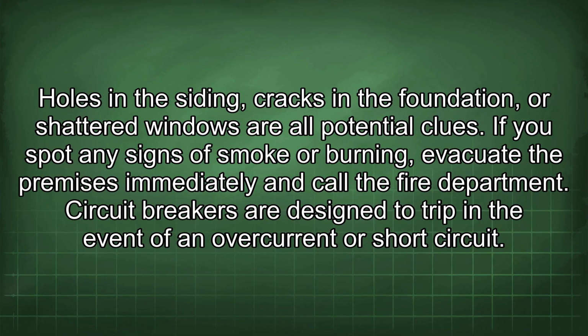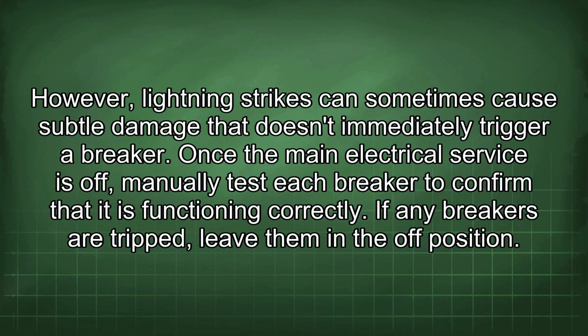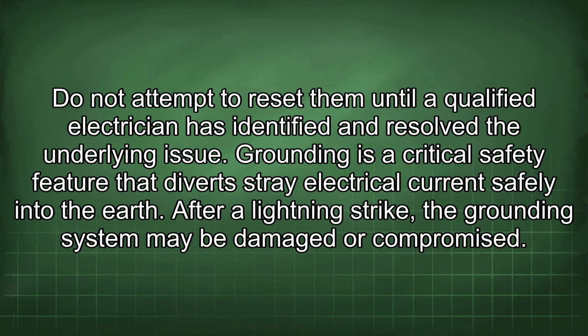Circuit breakers are designed to trip in the event of an overcurrent or short circuit. However, lightning strikes can sometimes cause subtle damage that doesn't immediately trigger a breaker. Once the main electrical service is off, manually test each breaker to confirm that it is functioning correctly. If any breakers are tripped, leave them in the off position. Do not attempt to reset them until a qualified electrician has identified and resolved the underlying issue.